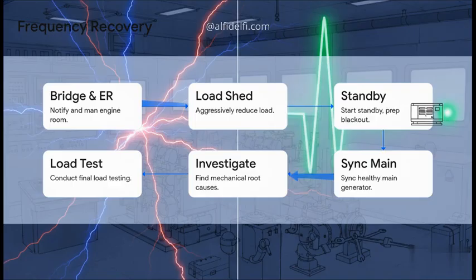Only once conditions are completely stable, or the blackout is safely cleared, can you restore the healthy main generator with full sync checks. Finally, you'll investigate the mechanical root causes in the governor or fuel system before doing your final load tests. Now contrast that with excitation recovery.